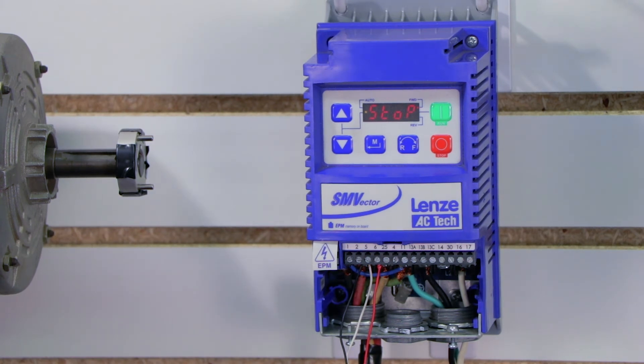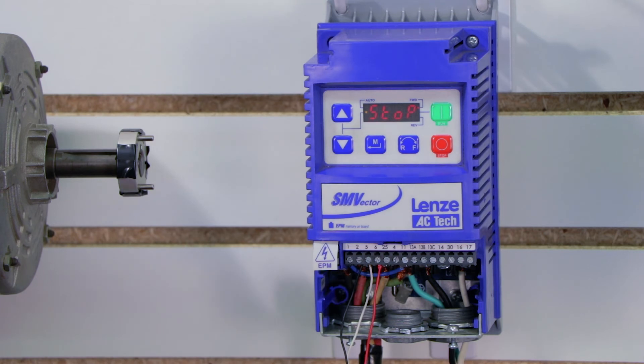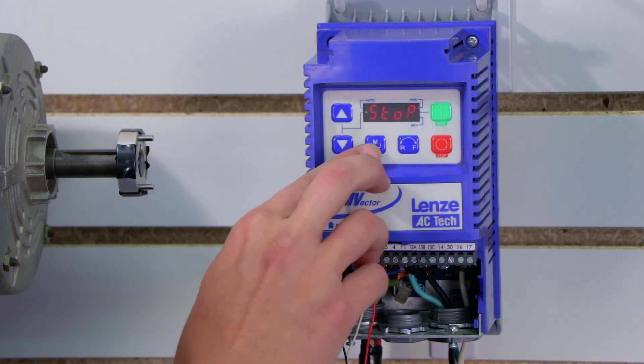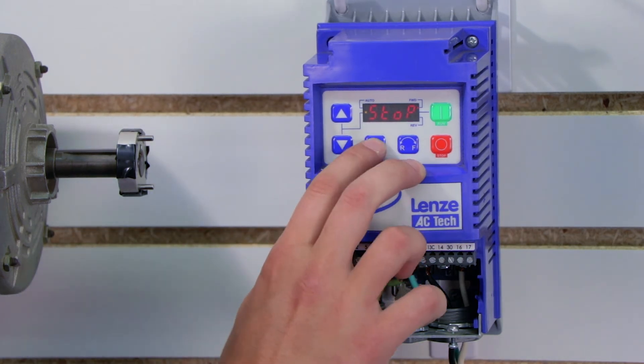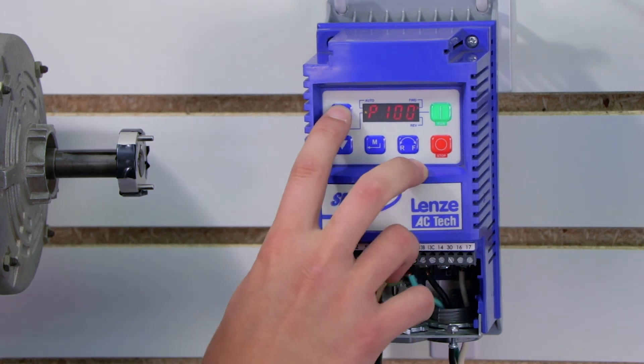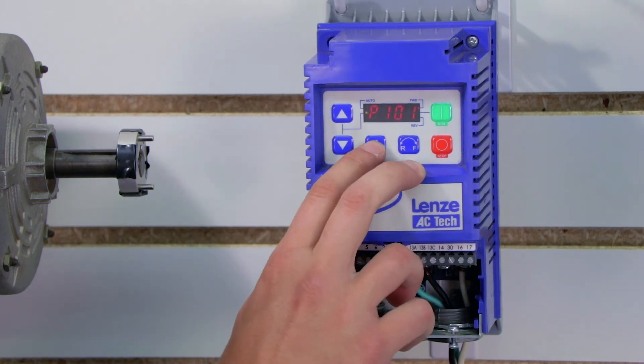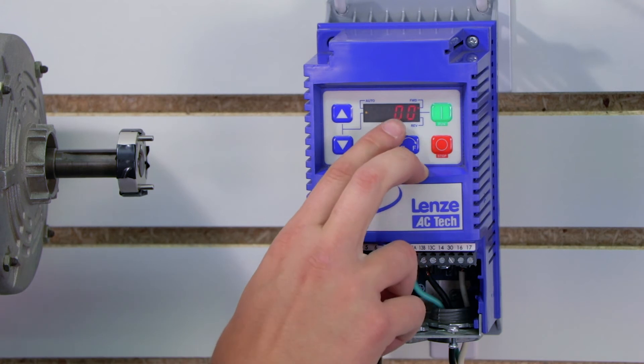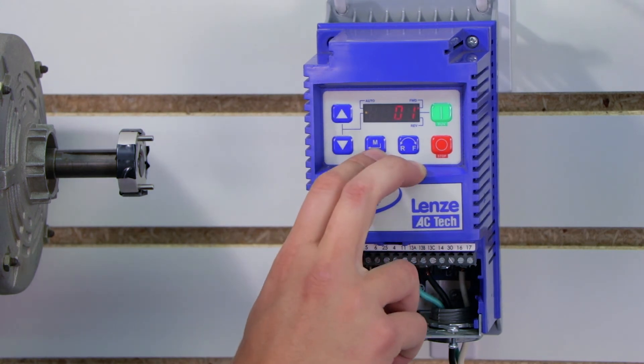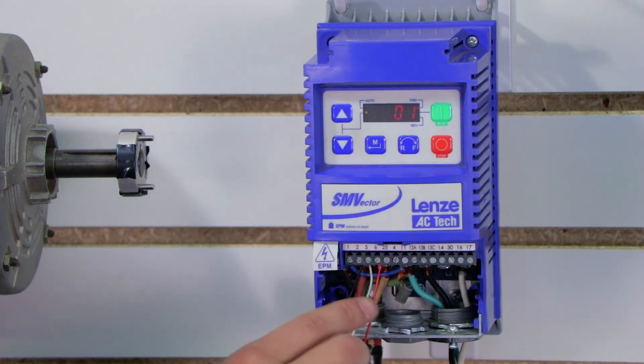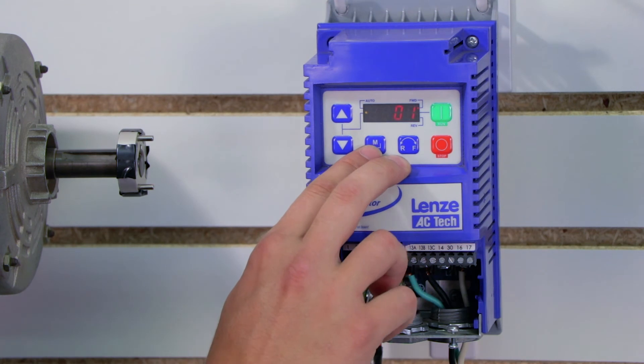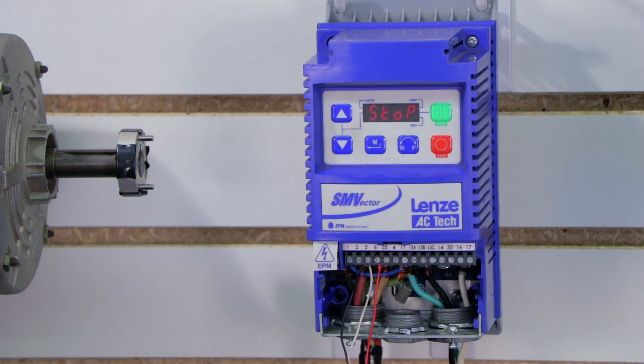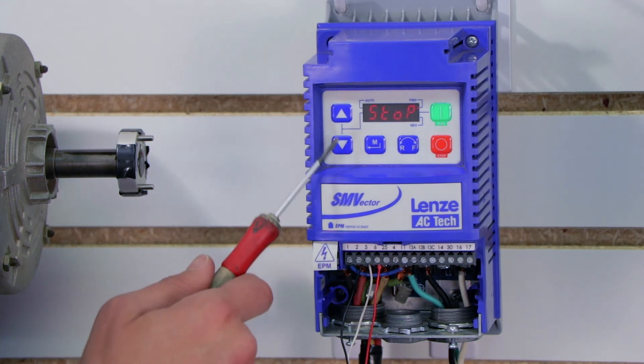After we do the wiring then we have to change one parameter and that's up here at the keypad. In order to bring up our parameters we have to press this M button and we got to go to P101 and press the M button again. By default it's set to look at the keypad which is zero zero for our speed, and we're actually going to tell it instead to look at our terminal strip or speed pot which is zero to 10 volts and press M.